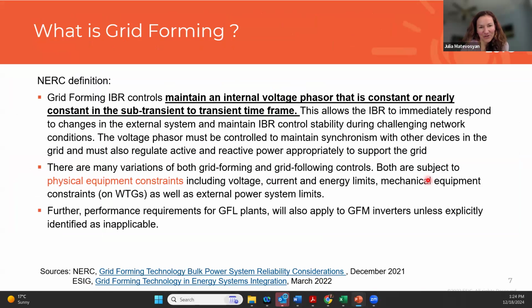Grid forming inverter-based controls maintain internal voltage phasor constant or nearly constant in subtransient and transient timeframes. So they basically act as a strong voltage source. This allows the inverter-based resource to immediately respond to changes in the external system and maintain inverter-based resource control stability during challenging network conditions. The voltage phasor must be controlled to maintain synchronism with other devices on the grid and must also regulate active and reactive power appropriately to support the grid. There are many variations of grid forming controls, and similarly there are many variations of grid following controls.